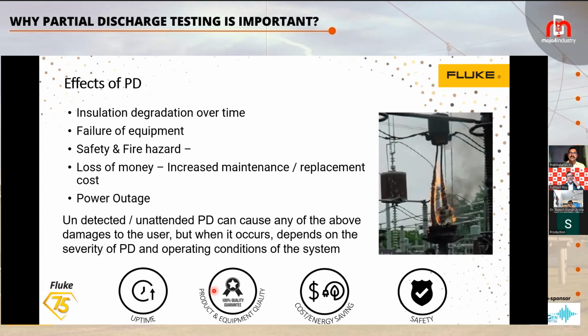And then more importantly, the power outage, because we are talking about high voltage equipments, which are usually used in the utility segments. And when the utility goes down, the entire country or the entire village or entire city goes down, and everything stands still, and it takes more time and money to bring it back. And as I put it here, the uptime: if you are detecting the partial discharge, then you can keep every machine and every industry running throughout, and the production and equipment quality can be improved. Then cost and energy saving: when your equipments are maintained well and in service, you are actually saving money.